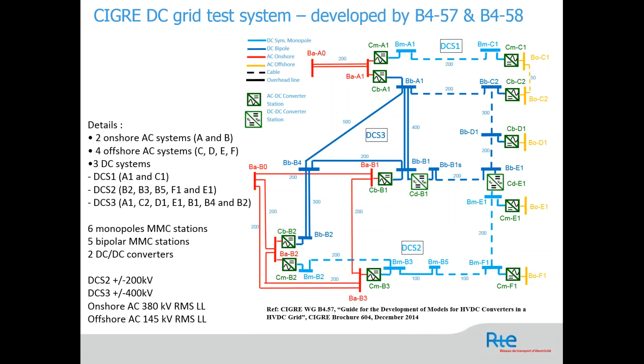So the question is, how do we model this DC grid in EMT software such as EMTP, PSCAD, HyperSim, or RTDS? Here is how it's been done in EMTP software. The DC cables, AC cables, DC lines and AC lines are developed using the frequency-dependent line and cable model, which is provided in all EMT software tools.